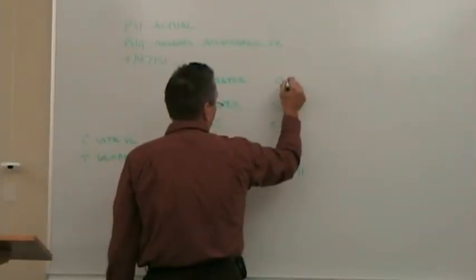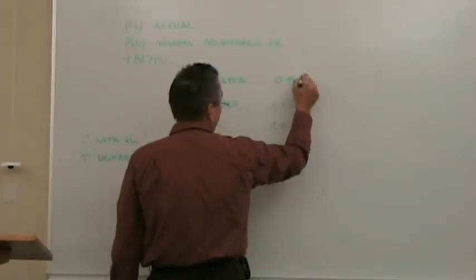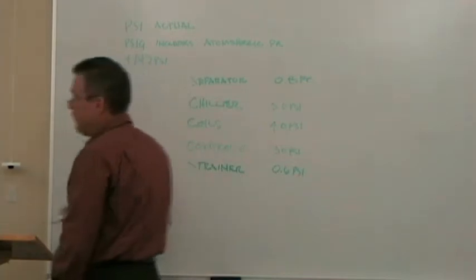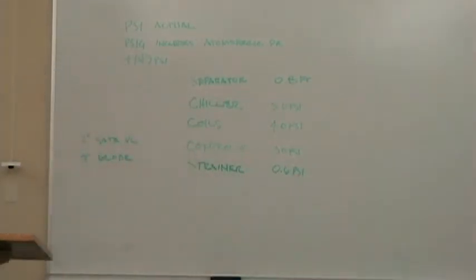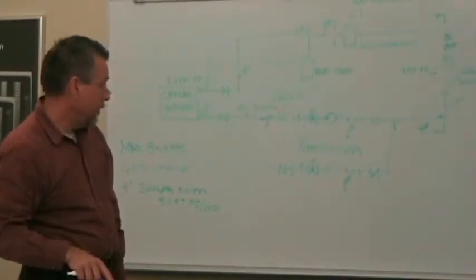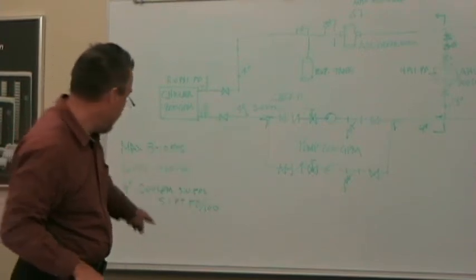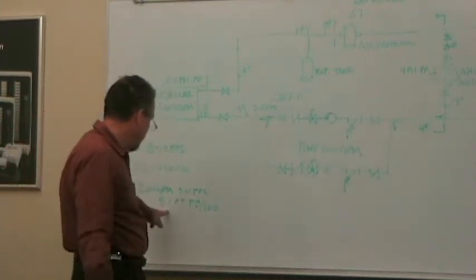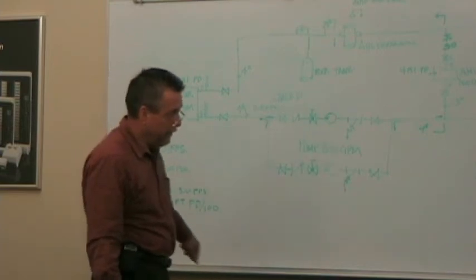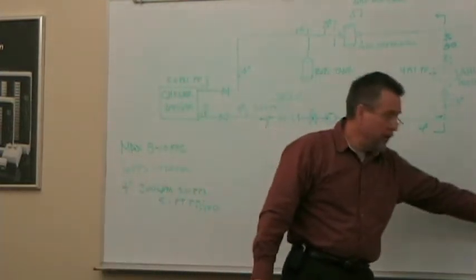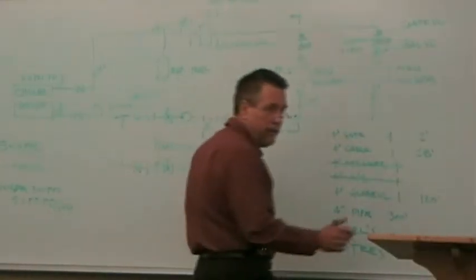It was 0.8 feet. Actual pressure drop, not per 100 feet, but actual pressure. And I'll show you how to convert feet to PSI. So in our pipe, we said was 5.1 feet per 100 feet. So what's 3 times 5.1? 16 point, or 15.3?